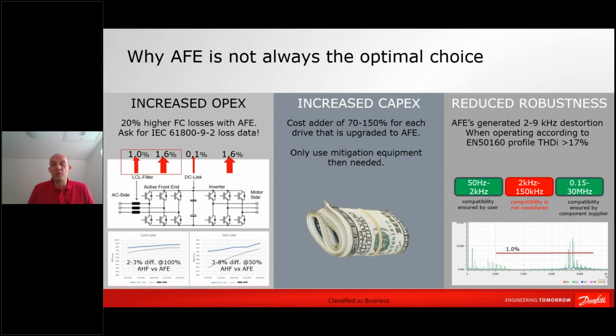last but not least, another thing you should be aware of is that the AFE solution is not removing harmonics. They are moving harmonics. So they are maybe cleaning up the lower frequency range, but then they are generating more noise in the higher order harmonic area. And this is something that you can do because there are no regulations in the 2 to 150 kilohertz area. Yet that will come. There is work in progress to improve this situation, but presently there are no standards in this frequency range, and that means that AFEs are actually allowed to generate a lot of noise on your power network in the higher order harmonics.